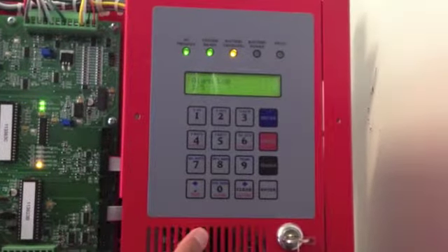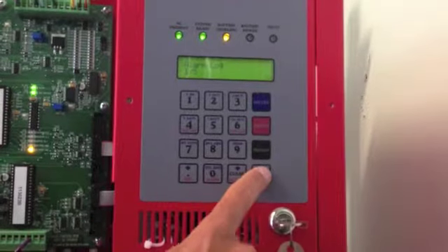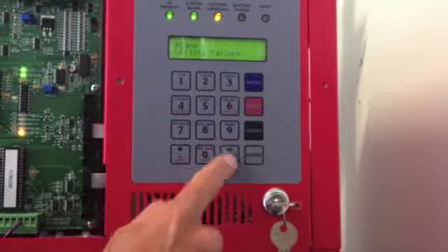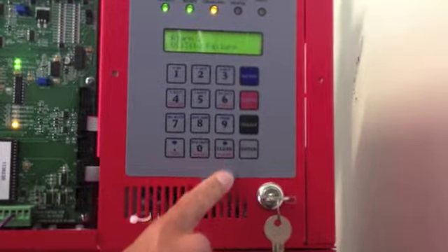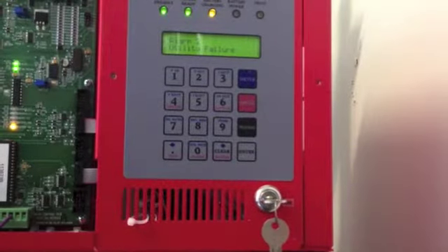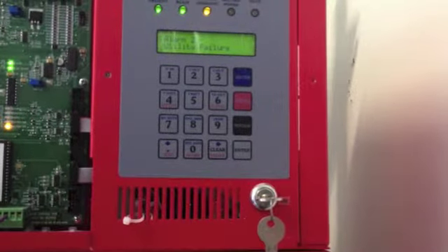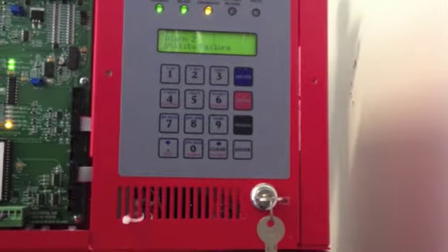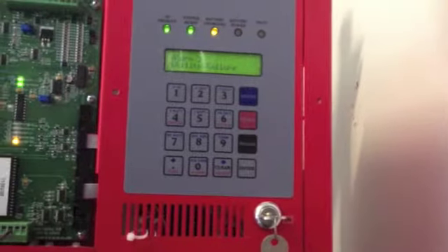And then our last log, the 0 key, is the alarm log. And we see 1 of 5. What I would do is just scroll through. We get a date, a time, and the alarm condition. And then we can look at all of them. Again, date, time, alarm condition. So what I'd be looking for there is what are my alarms. If all I see is utility failures, and again, they're not too frequent or for too long, no big deal, everything looks good. If I see alarms, you know, we have to take them as they come.